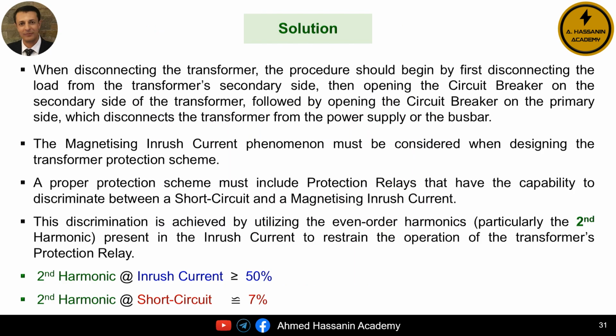We have understood together the dangers of magnetizing inrush current on the transformer, but now we want to know what are the treatment methods or suitable solutions, or how we can overcome the problem of magnetizing inrush current. The first step is, if the transformer needs to be disconnected for any maintenance, testing, or other work, we must first disconnect all the loads from the secondary side of the transformer. Then, the next step is to disconnect the circuit breaker on the secondary side, and the last step is to disconnect the primary side circuit breaker from the main bus bar that feeds the primary side of the transformer.